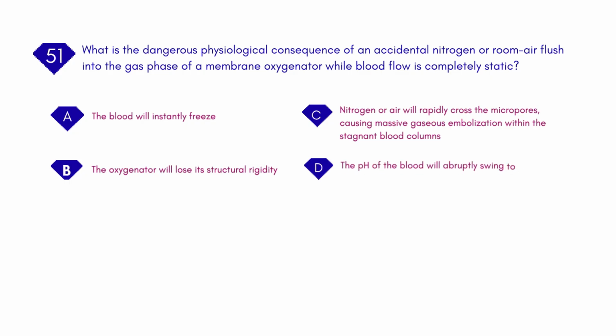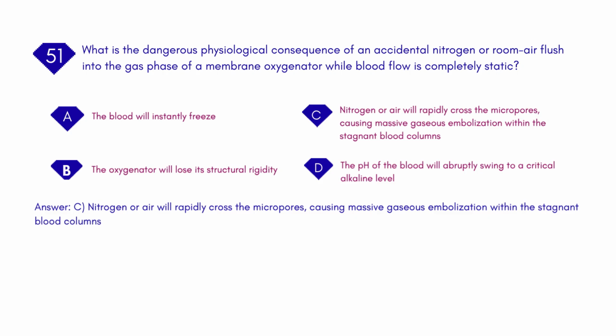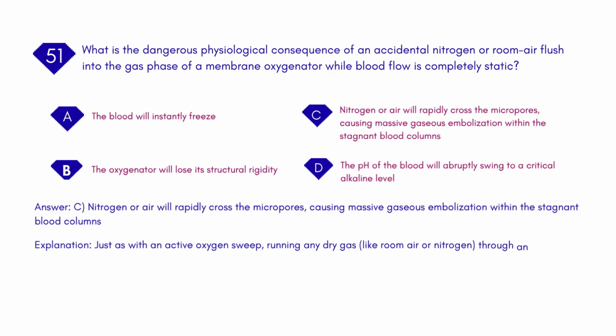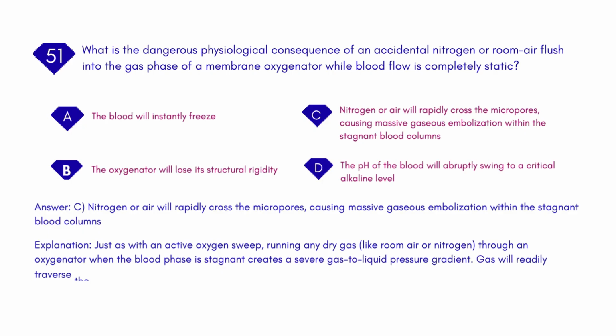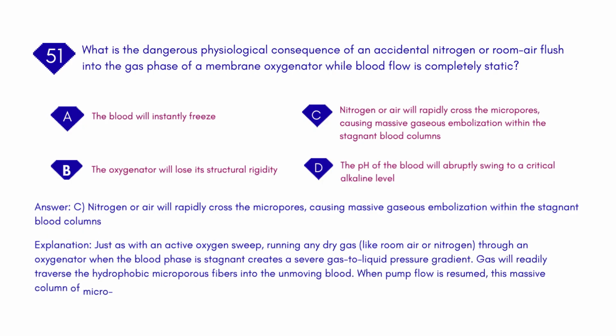D. The pH of the blood will abruptly swing to a critical alkaline level. Answer: C. Nitrogen or air will rapidly cross the micropores, causing massive gaseous embolization within the stagnant blood columns. Explanation: just as with an active oxygen sweep, running any dry gas, like room air or nitrogen, through an oxygenator when the blood phase is stagnant creates a severe gas-to-liquid pressure gradient. Gas will readily traverse the hydrophobic microporous fibers into the unmoving blood.